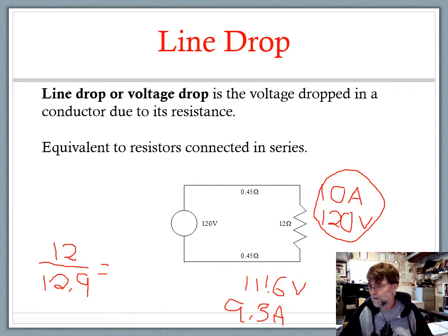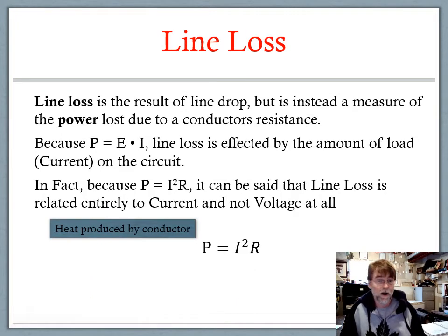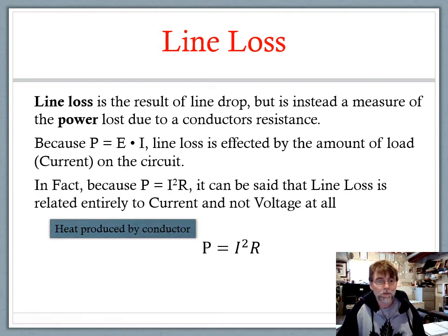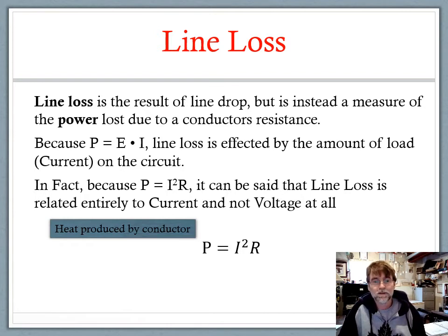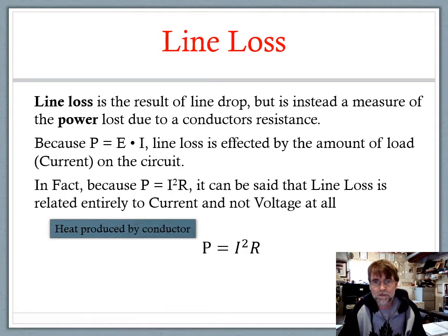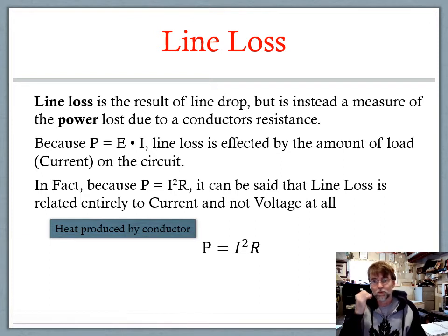Line loss is the result of voltage drop, but it is a measure of power. Because power considers both voltage and current, the amount of current is a really big deal. We can look at the power equation P equals I squared R — this is a power equation we haven't focused on much. When we talk about line loss and efficiency, P equals I squared R becomes the main factor. It can be said that line loss is related entirely to current and not voltage at all.